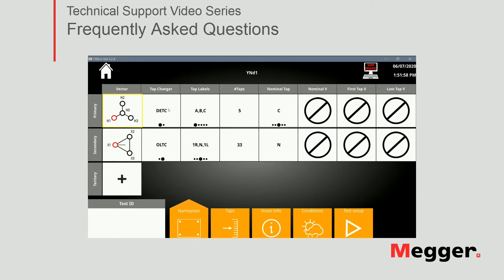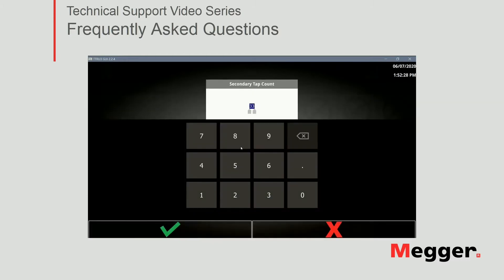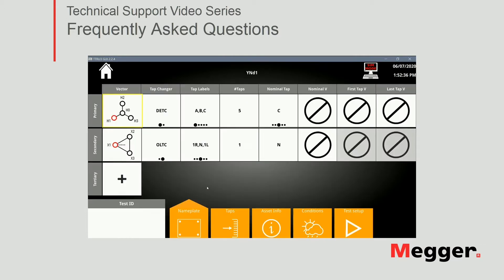Next, I need to tell the software if I have a tap changer and if so, what type. As you can see from our nameplate, we do have a DETC on our primary side and no tap changer on the secondary. Our tap changer on the primary is five taps, which is already selected since it's the most common. We have 33 OLTC options for the secondary, but in this case we have no tap changer. To tell the software I have no tap changer, I will set one single position on my secondary. I have no tertiary, but if I had one, this would be the place to add it to the test plan.